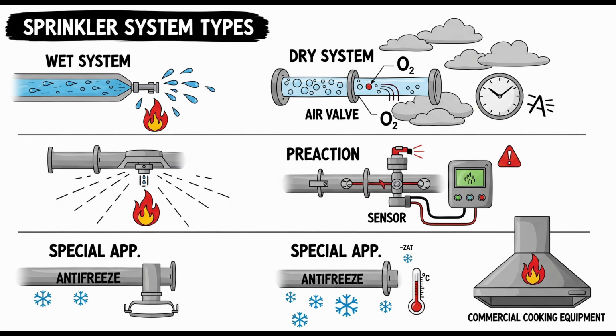This rapid venting forces the main valve clapper to trip open much faster than it would just from the system pressure dropping alone. So it speeds up that critical transition from air to water. Where do they connect? They must be located as close as practical to the dry pipe valve. The connection to the system must be above the priming water level of both the dry pipe valve and the QOD itself when the system is set.